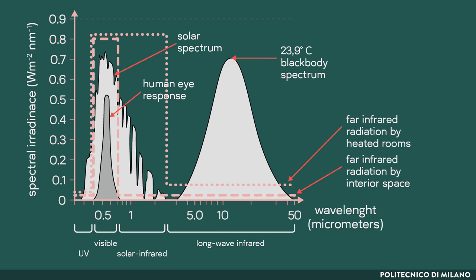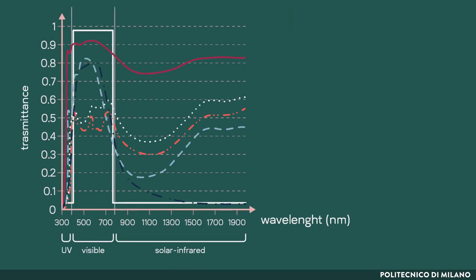The ideal glass in cold season should contribute to space heating and be able to block the far-infrared radiation emitted by the heated rooms. In the hot season, by contrast, the ideal glass should be able to block the near-infrared component of solar radiation to reduce heat gain and transmit the far-infrared radiation emitted by the interior space. In hot climates with high solar radiation, the ideal would be to use glass with low SHGC, but real glass with low SHGC also shows poor light transmission, which forces occupants to use artificial lighting or results in poor light quality.